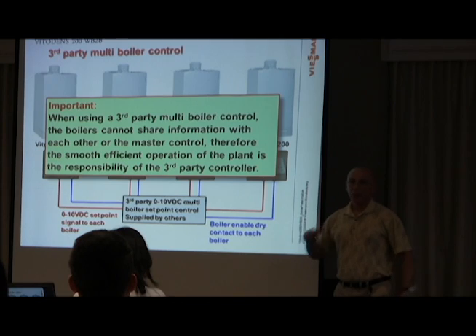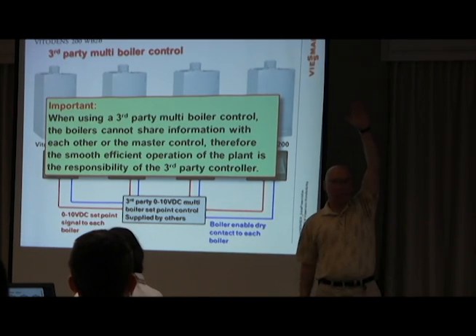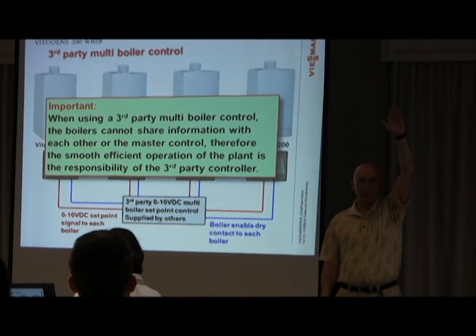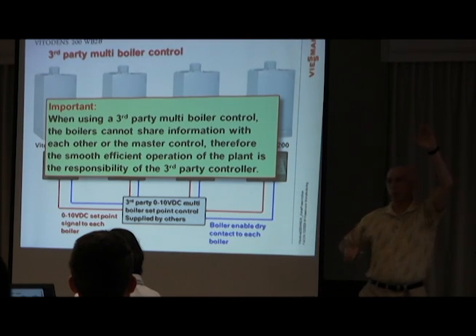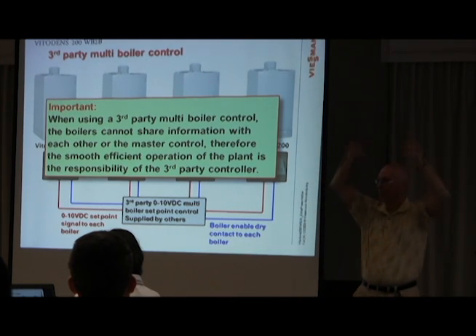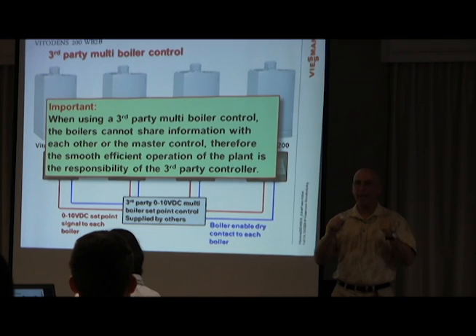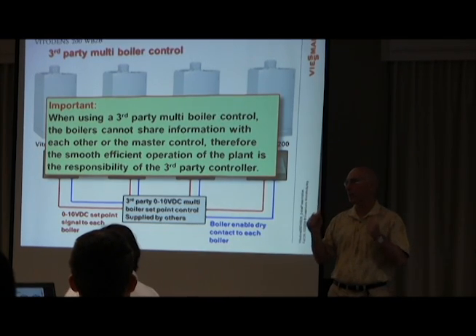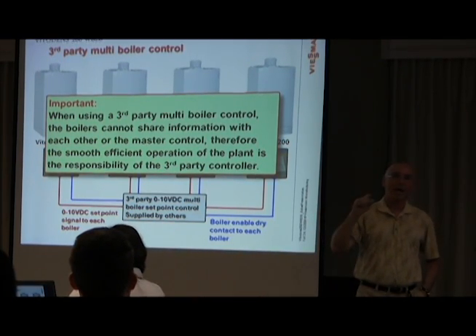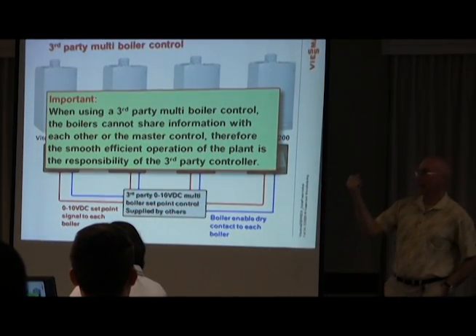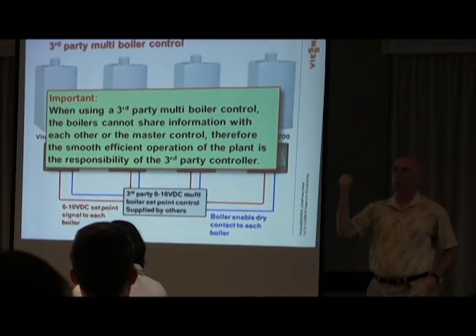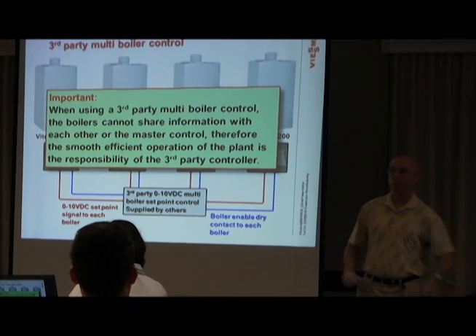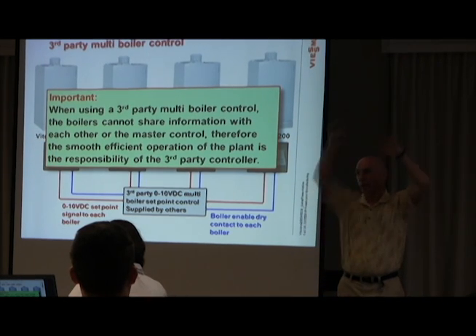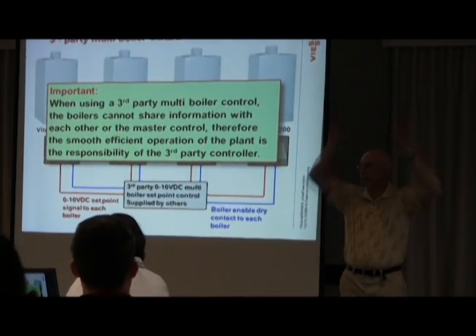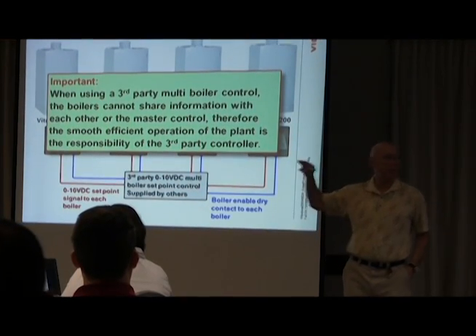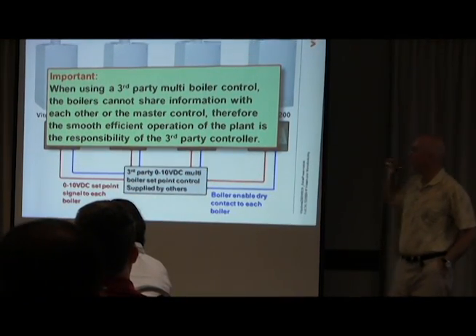If you put a third-party controller on, what happens is one boiler comes up, goes to maximum level, then the second boiler comes on, and it goes like that. So you're not getting full condensing potential. More boilers on at a lower modulation rate is going to increase your efficiency more than taking one up to high fire and then the next one come on, then that goes up to high fire. So it's better to keep them on even that way. So there's an advantage with the Viessmann controller.